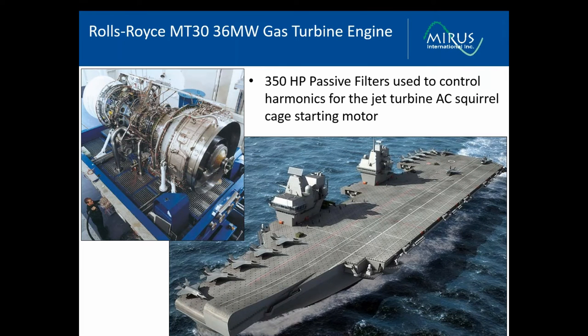In this example, 350 horsepower passive filters have been used to control harmonics on starting motors of the jet turbine propulsion systems on aircraft carriers. So these are obviously very large propulsion systems. The starting motors are a small component of the entire propulsion system, but our filters are a critical part of the harmonic mitigation for those.